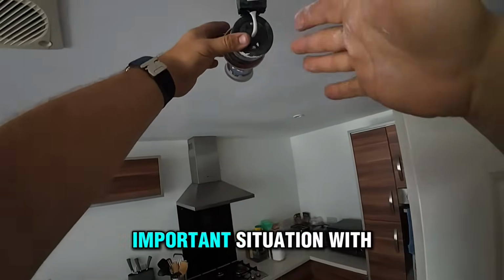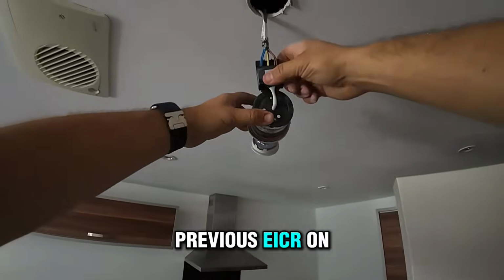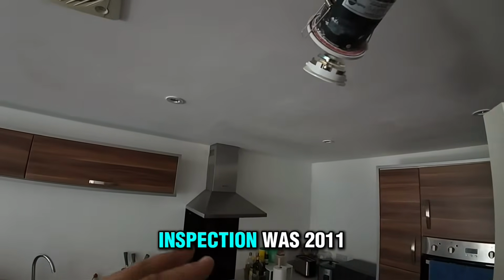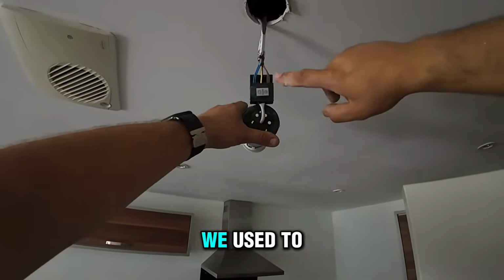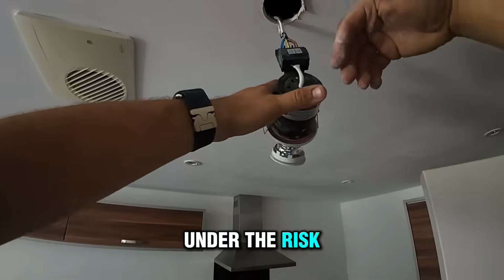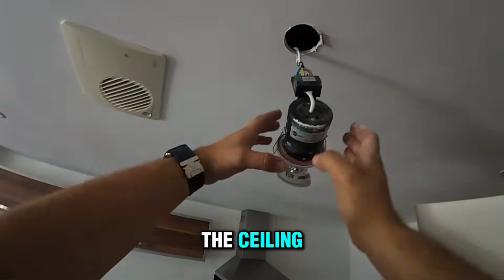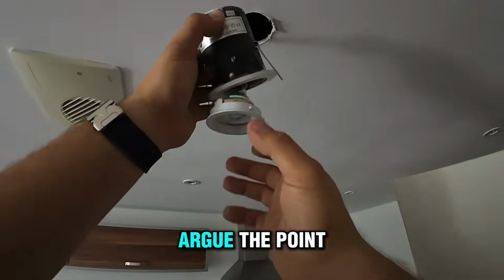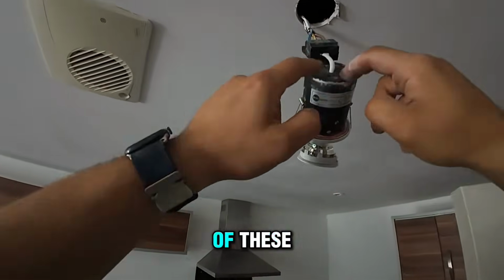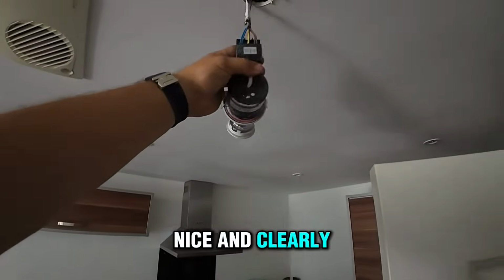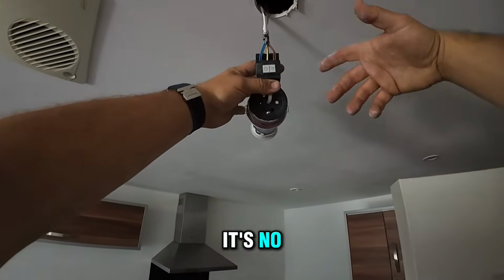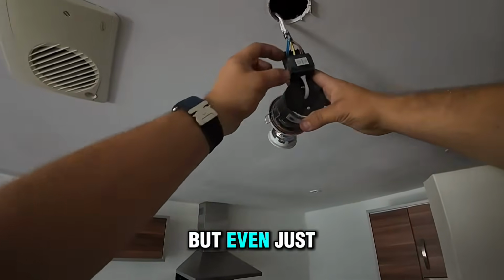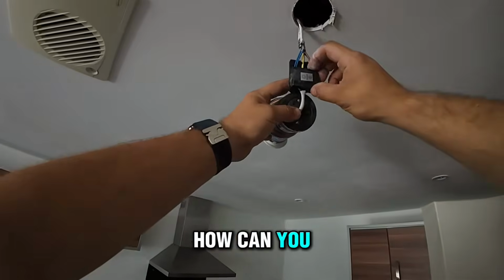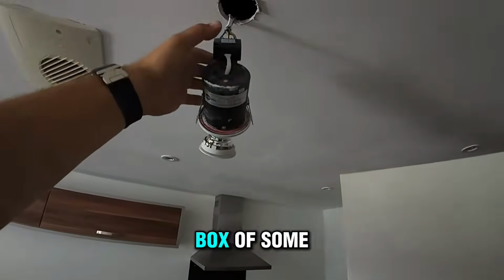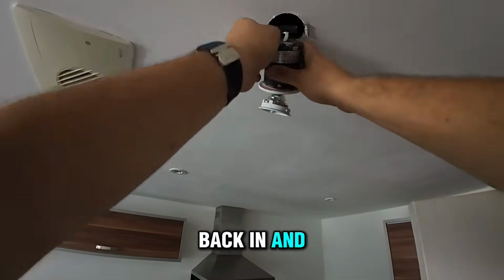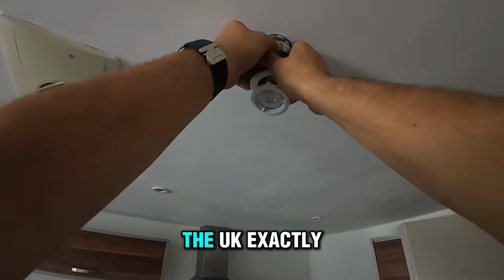This is one of the super important situations with the downlights. I recorded this recently on the previous EICR. On this occasion, everything is absolutely fine. So the last inspection was 2011. And that's how we used to be allowed to leave the connection under the risk assessment that it's not accessible because it's in the ceiling, it's a downlight, it's not something that you maintain. You could even argue the point that you can just change the light bulb without removing one of these. But actually, the regulation states now nice and clearly that single insulated cables outside the enclosure, it's no. Sleeve, tape, everything. So they've done what they could at the time. But even just to give them some credit, how can you terminate both cables into that termination? You can't. You need a junction box of some sort beforehand. So this goes back in, and I'm sure there will be a million other houses in the UK exactly the same.